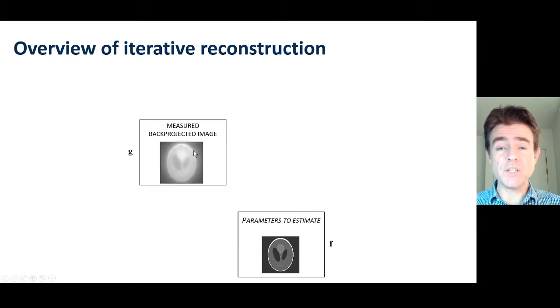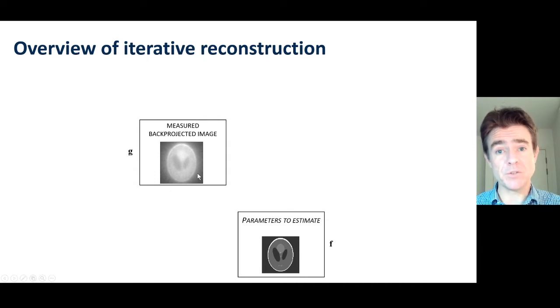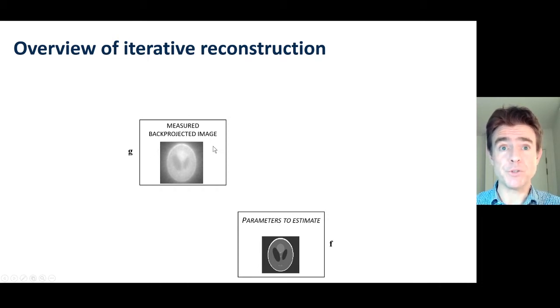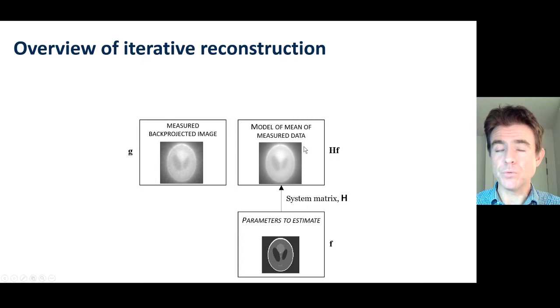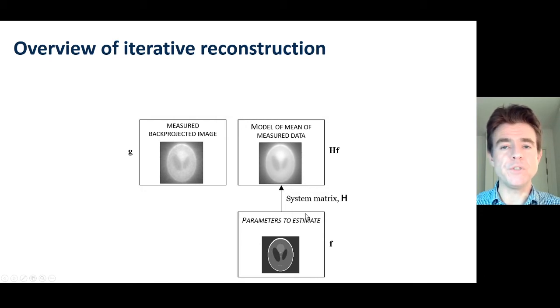Then we have some measured data. Up to now we've been focusing on the case of back-projected data, but in this video I want to connect us back to sinograms as well. Whatever the measured data, that is obviously involved in iterative reconstruction, whether it's in sinogram form or back-projected image form. Then we need some model of how to get from the parameters to a model of the mean of the measured data. When we do this forward model step, it is always for the mean of the data. We model the noise separately through the objective function.